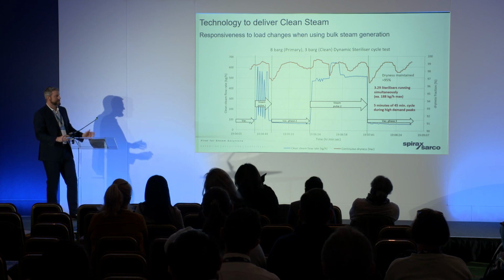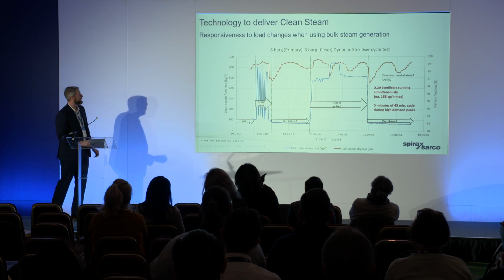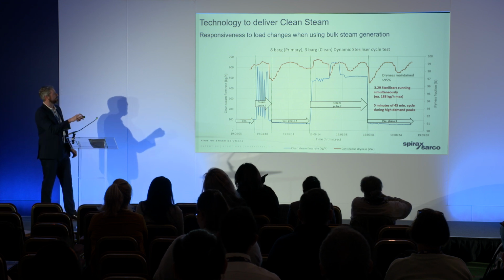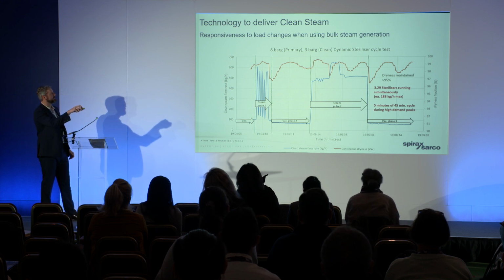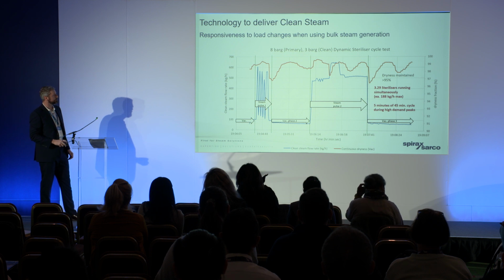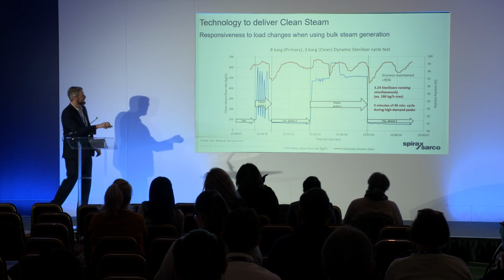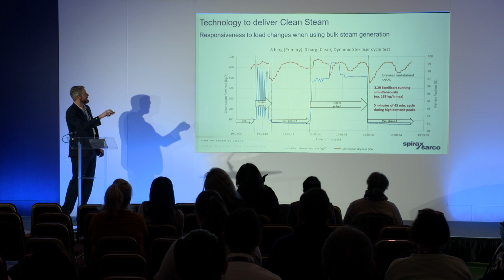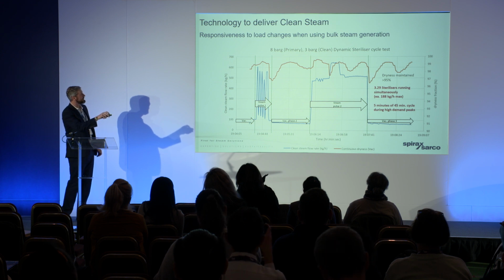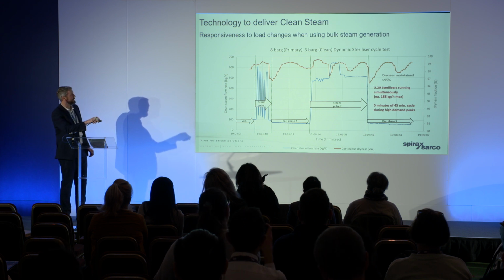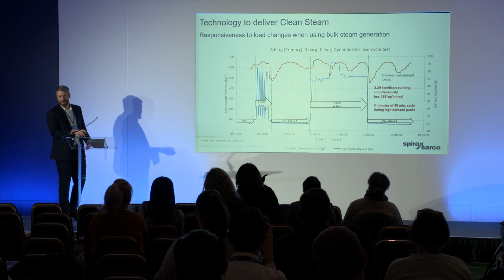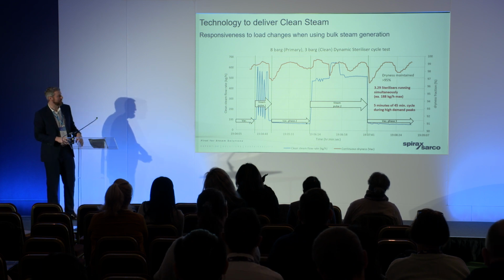This slide zooms into 5 minutes. This is an 8-bar plant steam generating 3-bar clean steam. You can see here that these are the real spikes. So we were able to go up to 620 kilograms an hour, which was 3.29 sterilizers running at the same time.